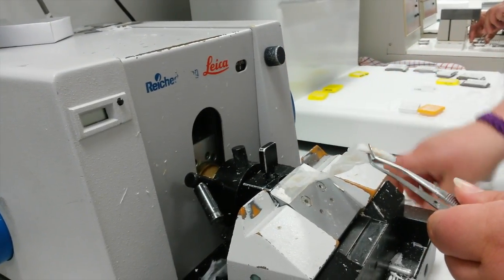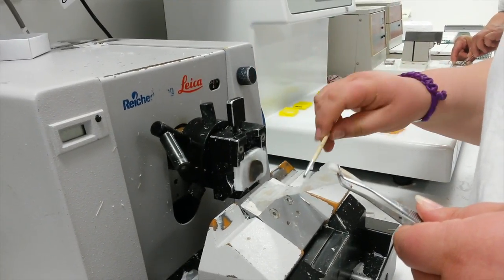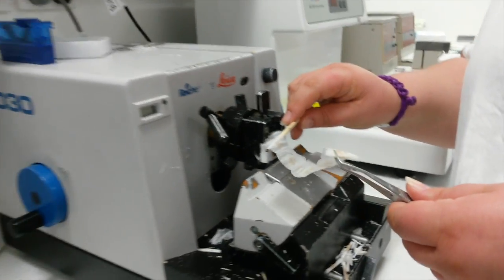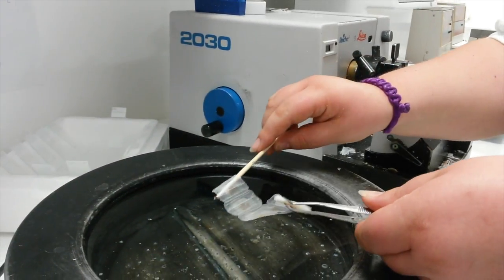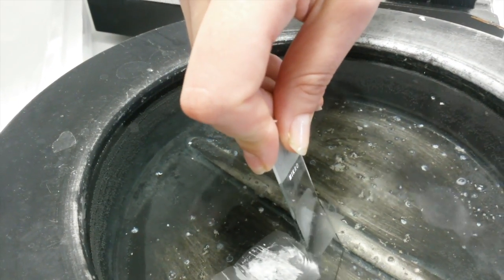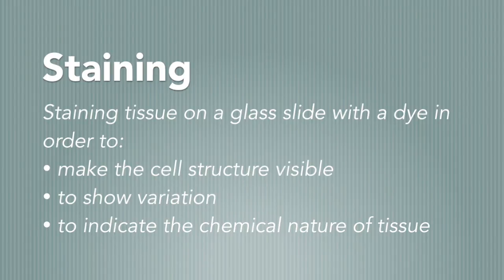The microtome has a screw thread that advances the block toward the blade by 3 to 6 microns per rotation. The paraffin block must be very cold in order to be cut correctly. Once cut, a ribbon of sections is floated onto a water bath. Glass slides are able to pick up each individual section and are dried on a hot plate or incubator before moving on to the next stage: staining. Staining refers to the process of staining tissue on a glass slide with a dye in order to make the cell structure visible, to show variation in these structures, and to indicate the chemical nature of the tissue elements.